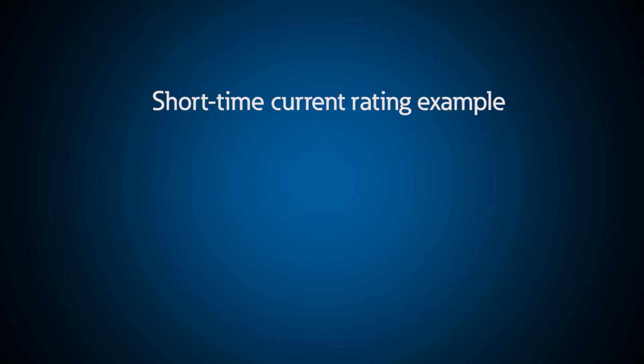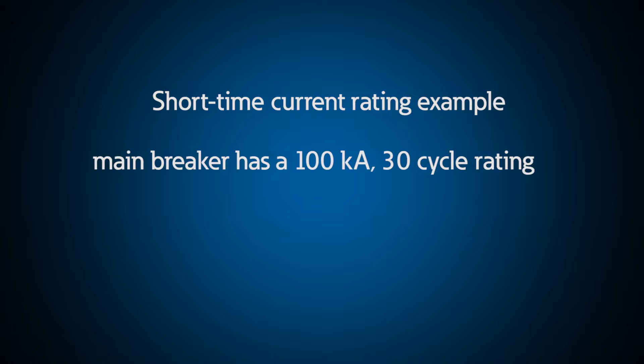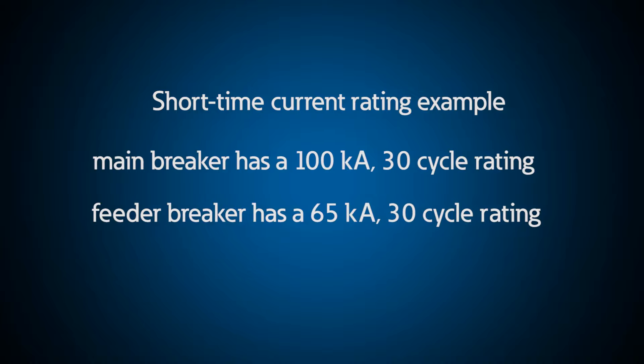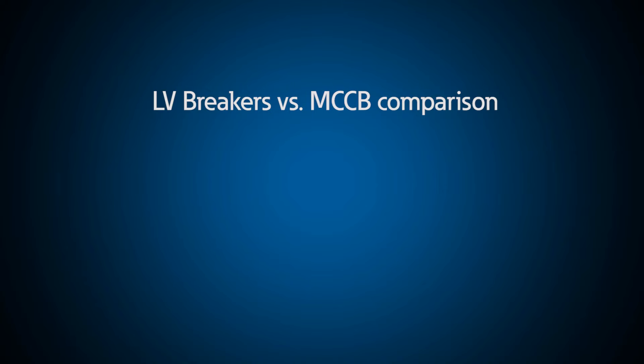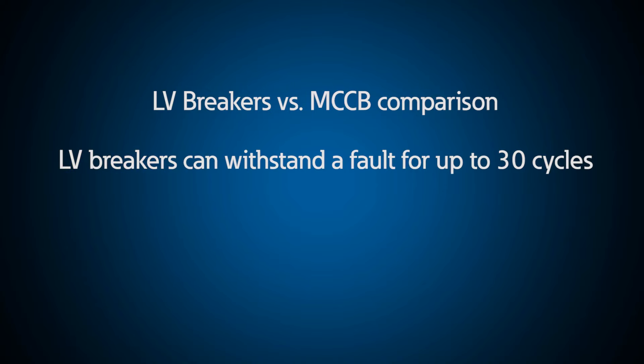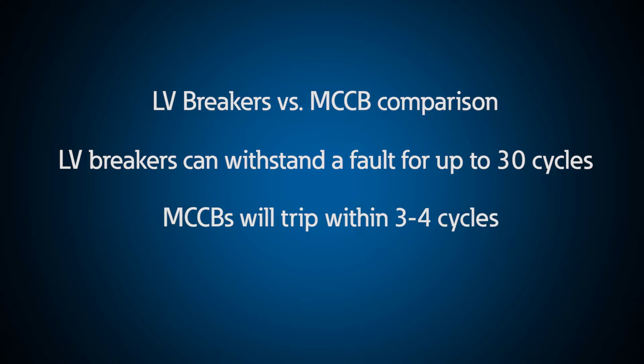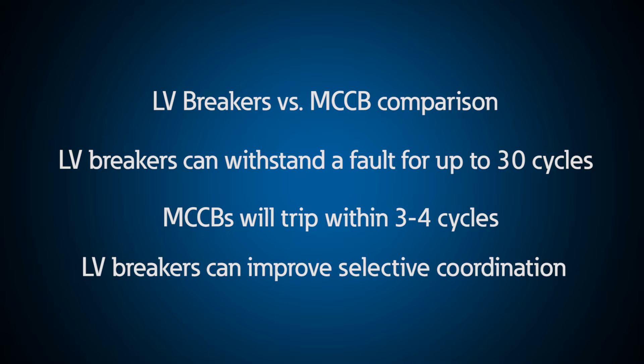For example, if the main breaker has a 100 kA 30-cycle rating but a feeder breaker has a 65 kA 30-cycle rating, the switchgear will carry a 65 kA 30-cycle short time withstand current rating. Low voltage power circuit breakers are specifically designed to withstand a fault of a given magnitude without tripping for up to 30 cycles. Compare this to molded case circuit breakers or MCCBs, which are designed to trip instantaneously within three to four cycles when subjected to fault current above the instantaneous setting. As a result, MCCBs are tested to withstand a short circuit fault for only three cycles before tripping.